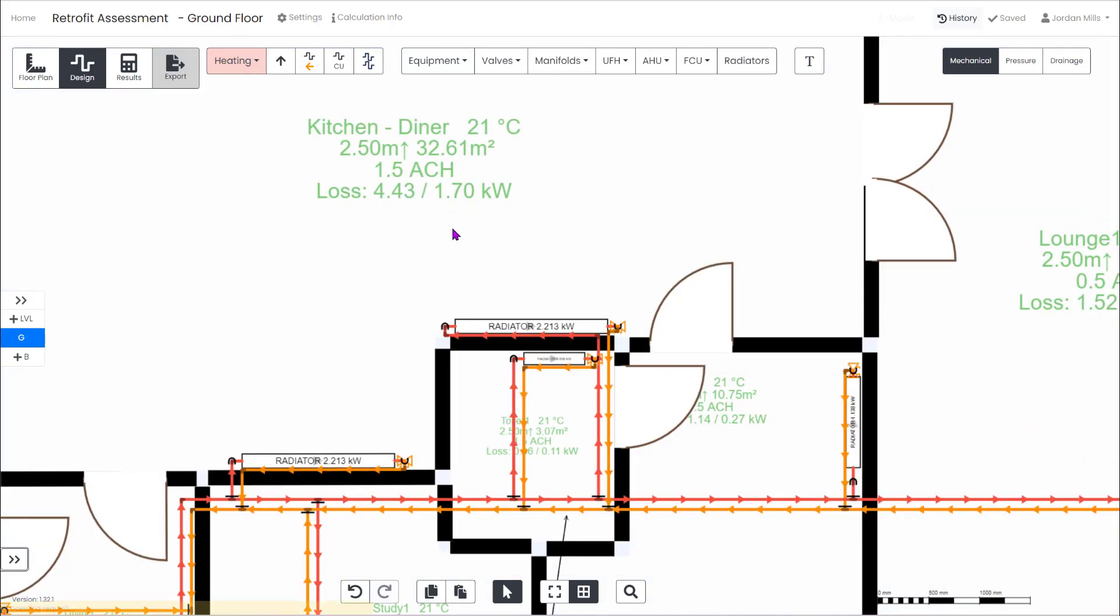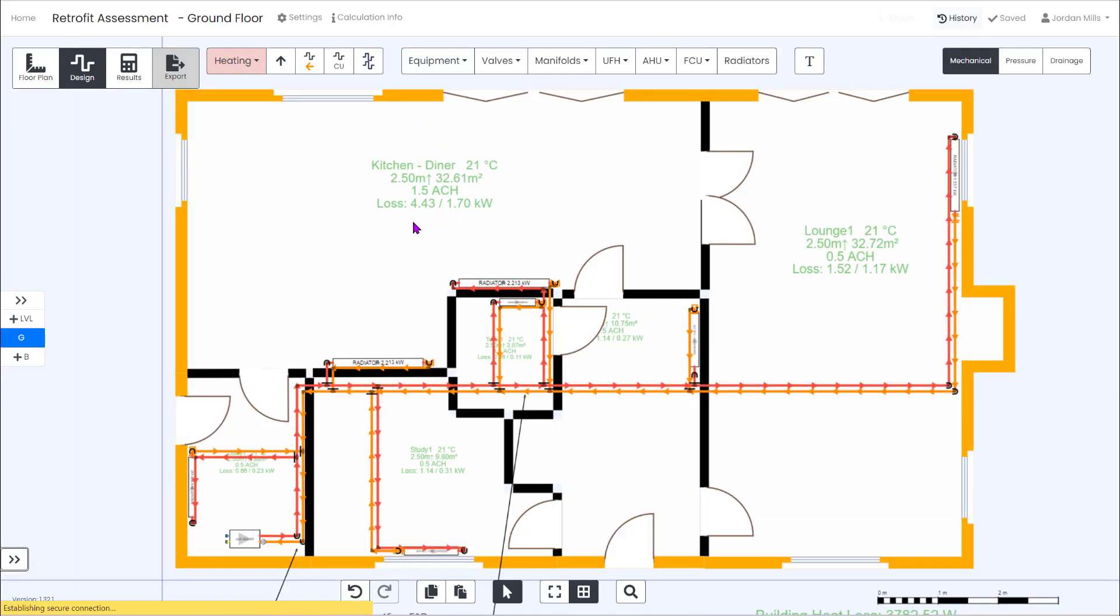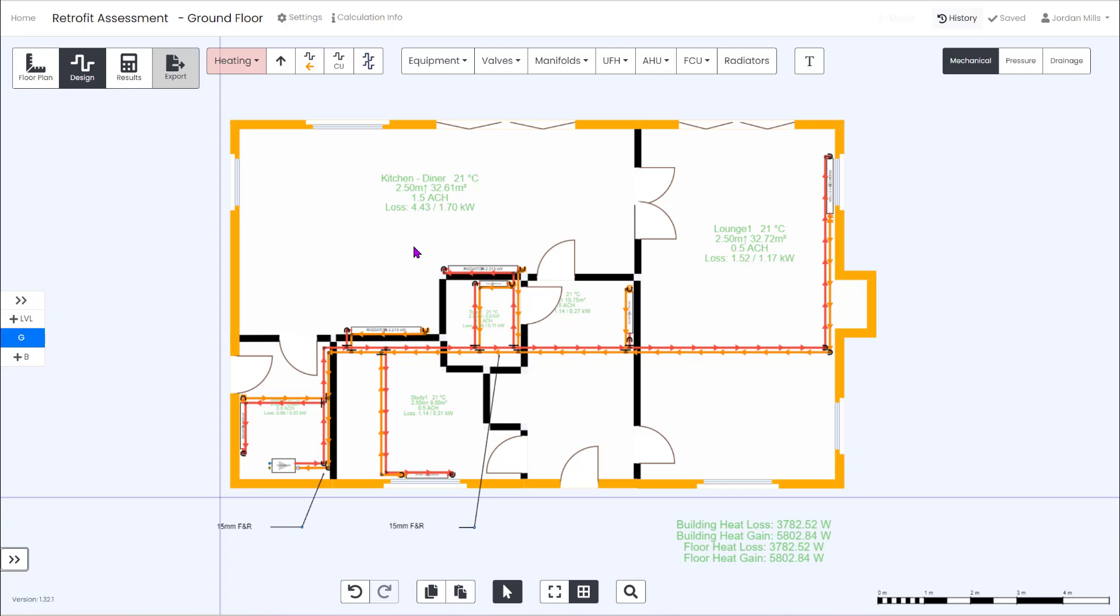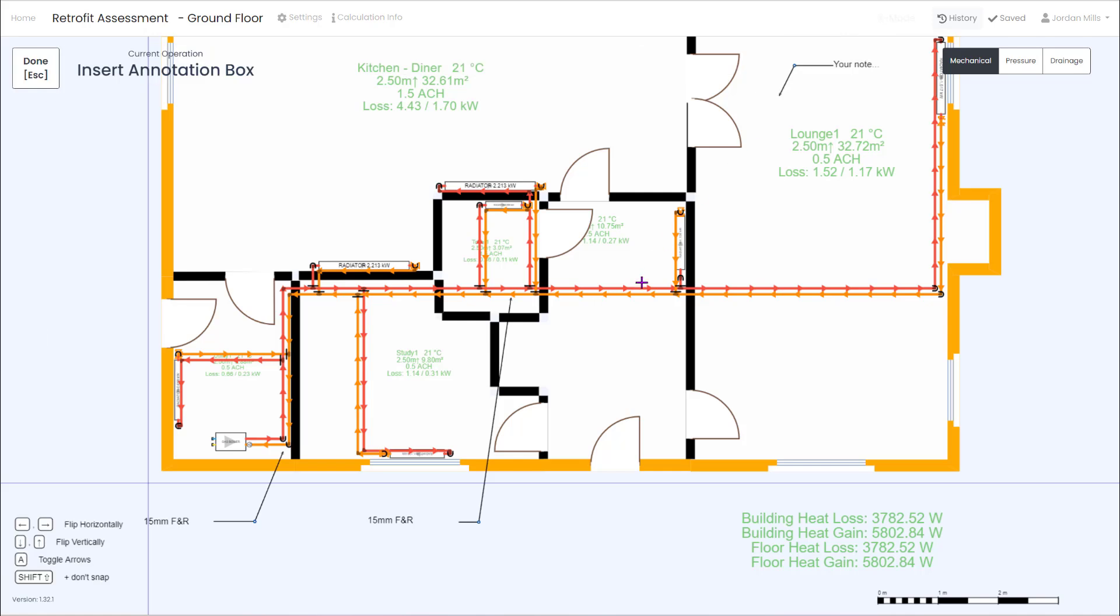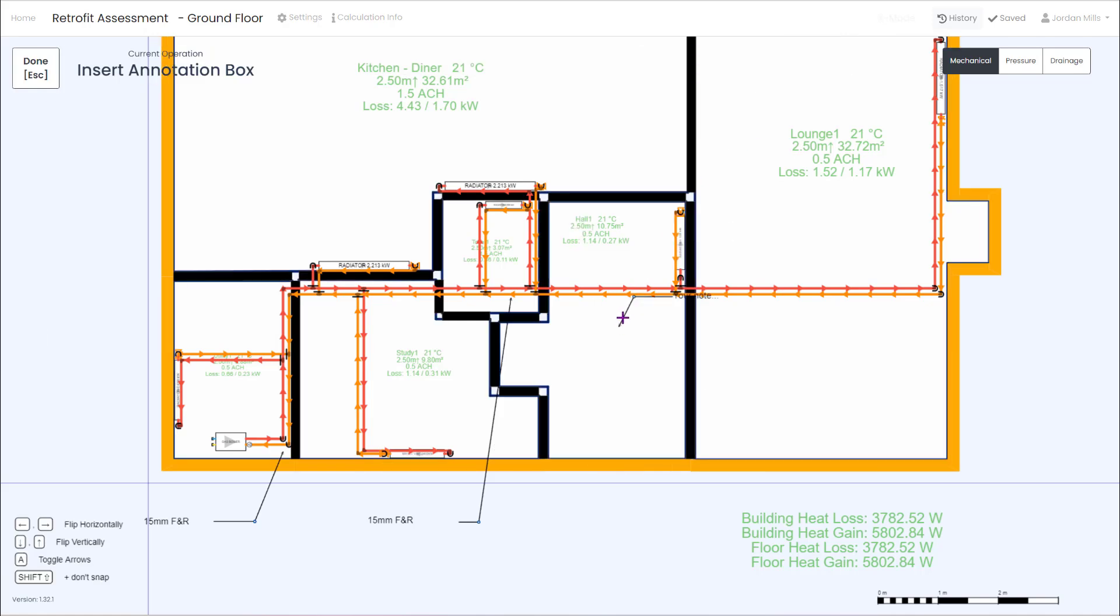Looking around the building we can see green text in every room which indicates the heat demand is satisfied, especially in the kitchen diner where the two existing radiators can supply up to 4.43 kilowatts at a DT50.